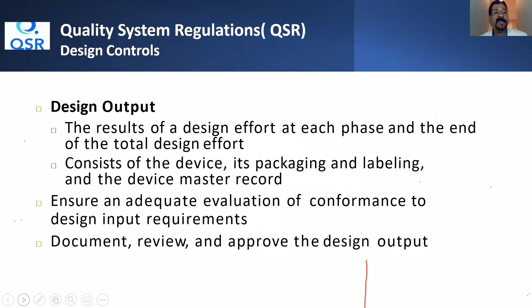Now, design input, output, user needs, and what is design output? This design input requires minimum and maximum dose delivery of the drug, viscosity, and desired requirement of the delivery rate, as we have just discussed, right? So the drawing specification, syringe dimensions for the syringes, the needle bore, gliding force for the plungers, content and fill level of the prefilled syringes, labeling, packaging and labeling specification for the prefilled syringes, specification for the drug-contacting syringe material. This all falls under the design output requirement. We just discussed that. I just gave a brief in a table of comparison.